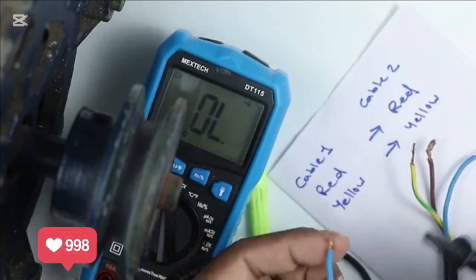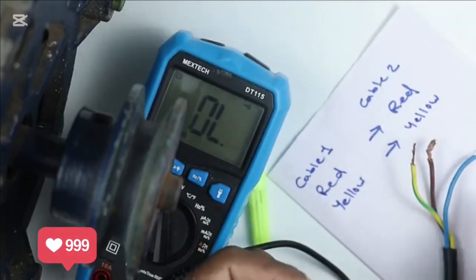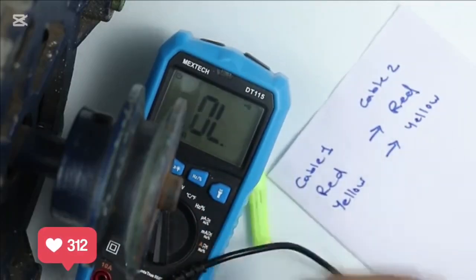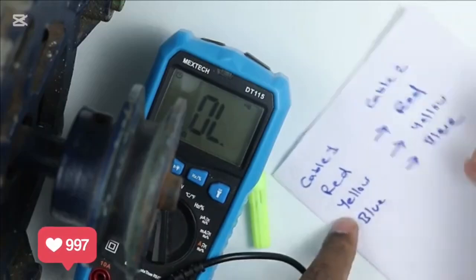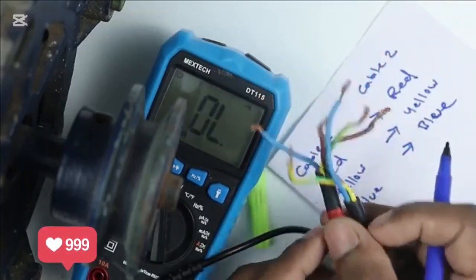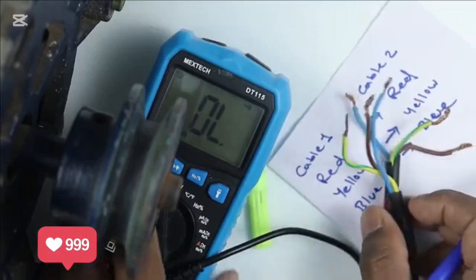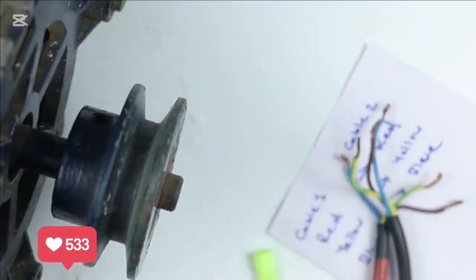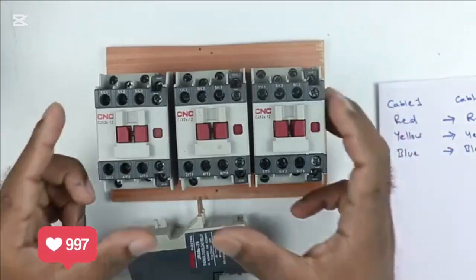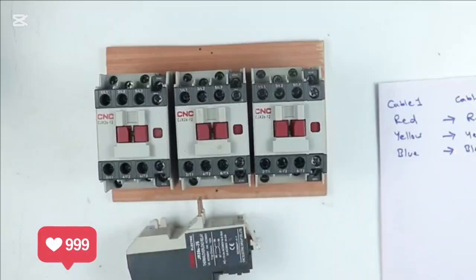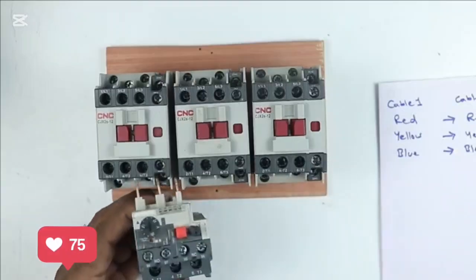We checked the red wire and the yellow wire. The blue wire is left. Let's check this. We are getting continuity of the blue wire with the blue wire. So here, according to color coding, the wires are connected. After this identification of the wires, you can start the connection of the motor. To make a star delta starter, you have to use a total of 3 contactors and an overload relay.